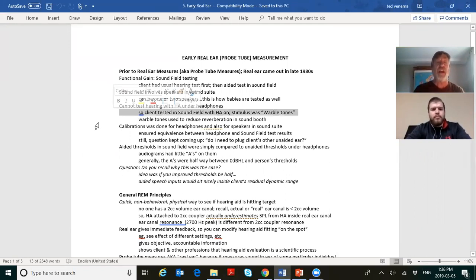Calibration is always done for the headphones and also for the speakers, and so they were still putting out the same intensity, like 60 dBHL at 1,000 hertz under headphones was equivalent to 60 dBHL from the speakers, as long as you were within 1 meter of the speaker. So it ensured equivalence between the headphones and the sound field test results, but still the question kept coming up, do I need to plug the client's other unaided ear? Anyway, aided thresholds in a sound field were simply compared to unaided thresholds under headphones, and as we saw, the audiograms had little A's on them.